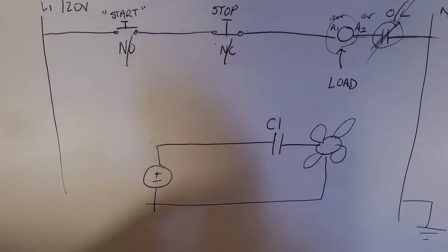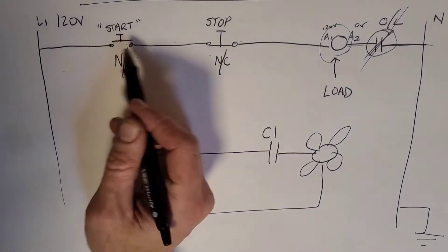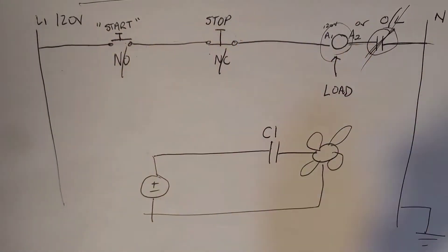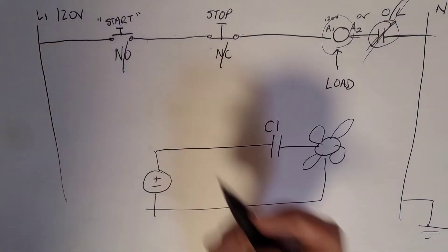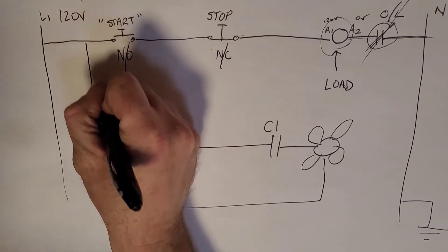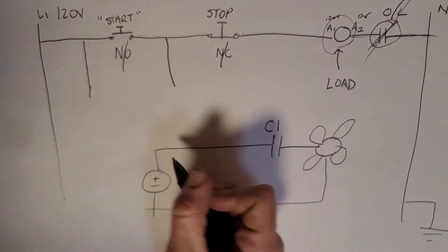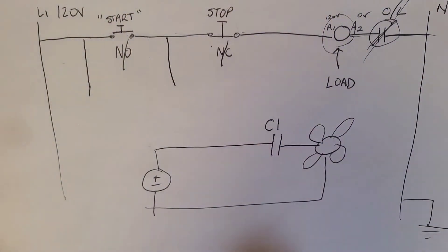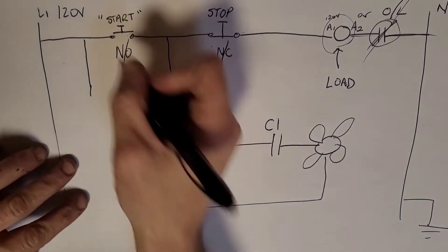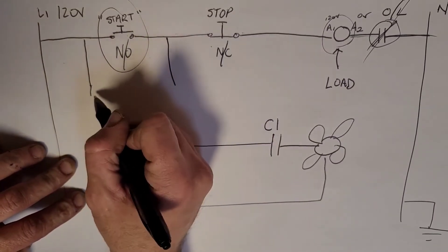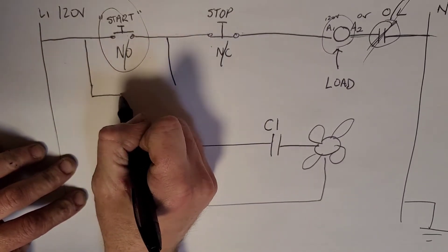But I don't want that. I want this to stay on, but it won't. Why? Here's why: these are momentary push buttons. When you push this in, this circuit closes. When you let go, that circuit opens. What we can do is make a parallel branch. When you say a parallel branch in controls, I want you to think OR. We're going to make an OR branch.